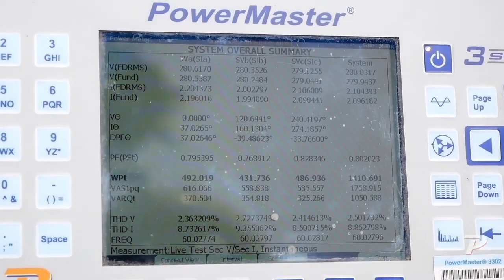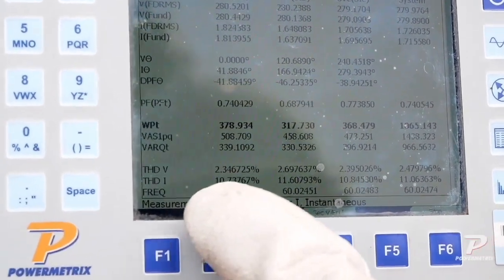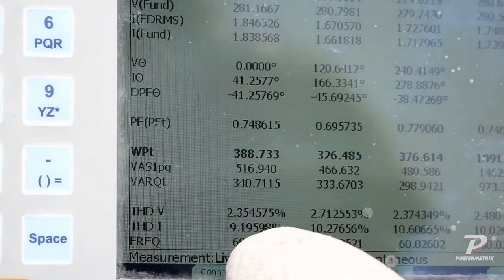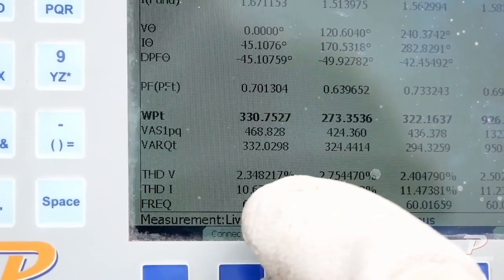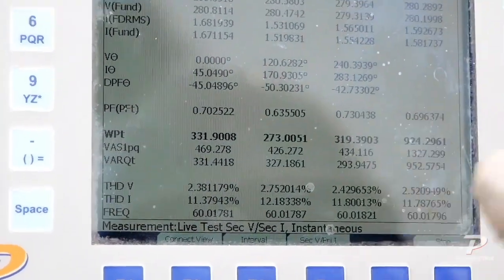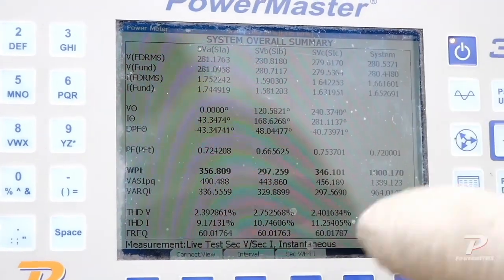You can notice down here at the bottom, the current is getting up to 12, 10 - it's getting kind of high on the Harmonics for the current. The voltage, I'm not seeing a number that high. Remember, it's V8 - I remember it by the juice, I need something from my P-brain to remember it. If it's over 8% on the voltage, it's bad, but we're not seeing that too much here.